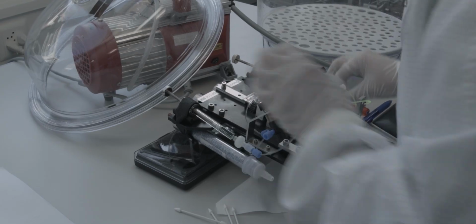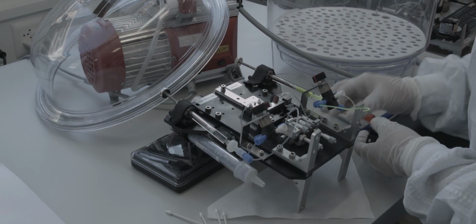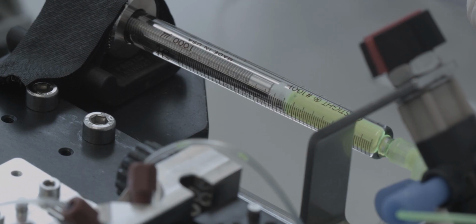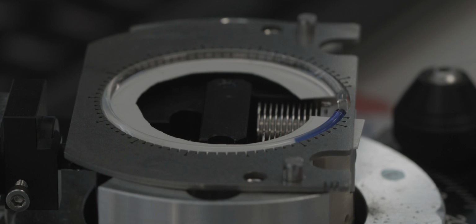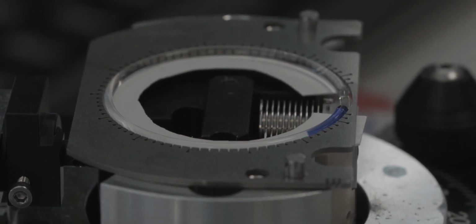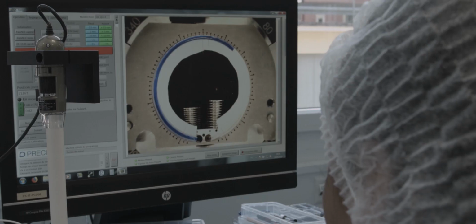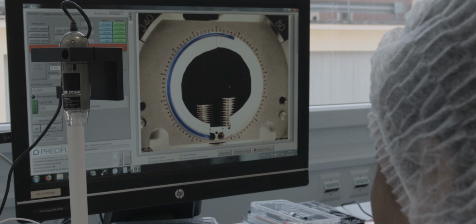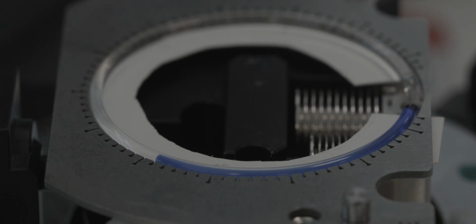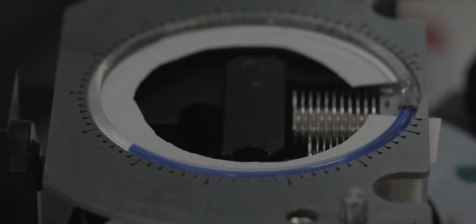All the fluidic devices that we produce are tested. They follow a very intense process of testing, and one of the processes is the cycling. So we put our fluidic device at different temperature ranges. You know that the liquids react a lot with the temperature, and we have to make sure that at 10 degrees, 50 degrees, etc., the fluidic device works correctly.